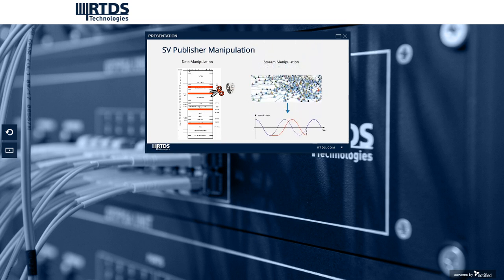The second type is stream manipulation. We know SV packets travel through the Ethernet network from point A to point B. The Ethernet network is dynamic and changing all the time. For example, if the network is pretty busy, then it could cause noticeable delay in the subscriber. This represents the second type of manipulation.